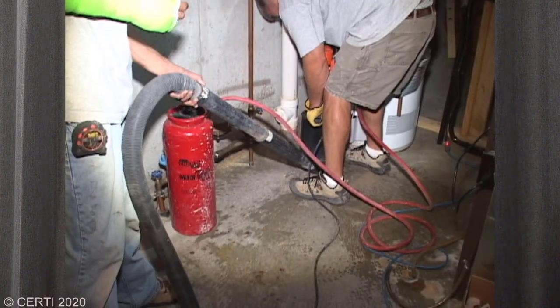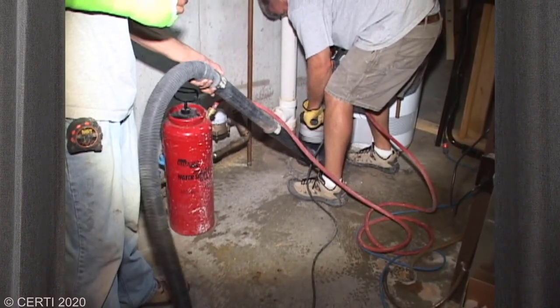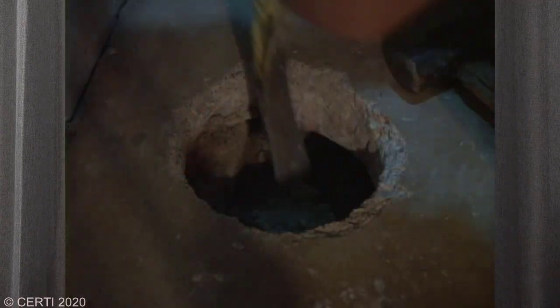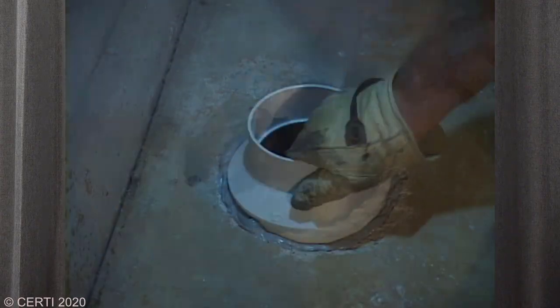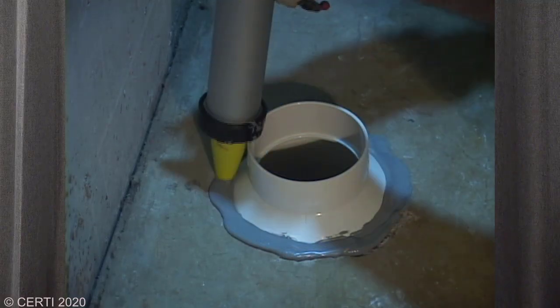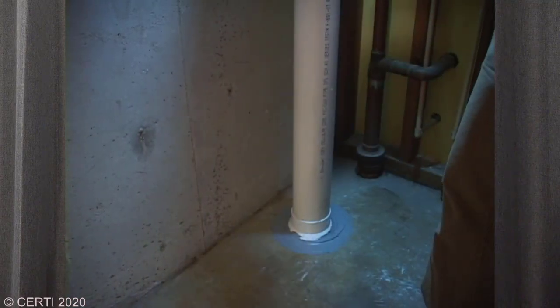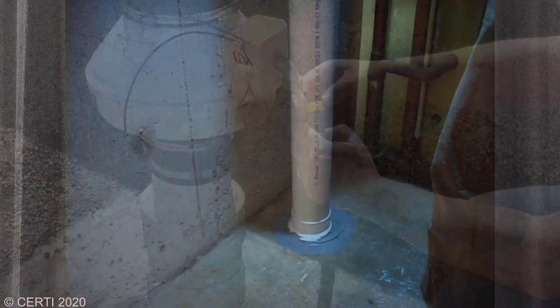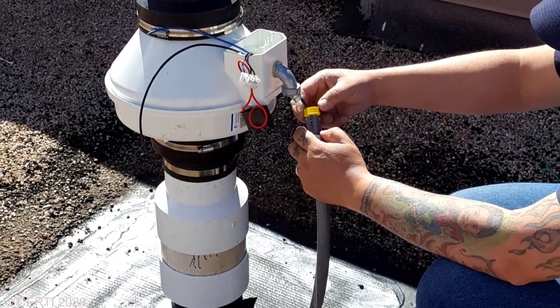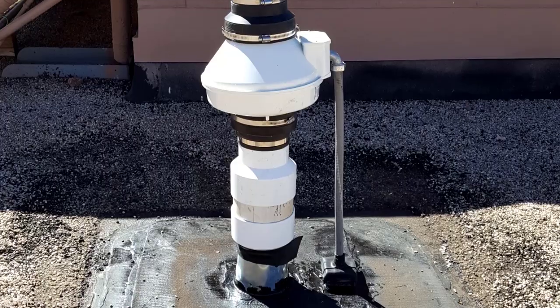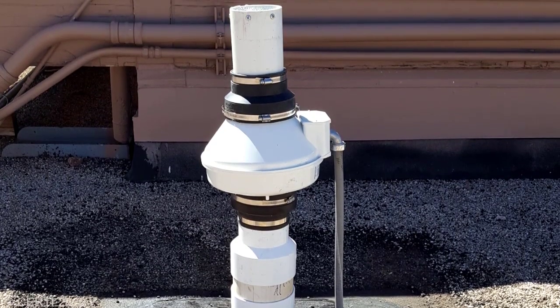For a slab foundation, a hole is cored through the slab at a strategic location. A couple buckets of dirt are hand excavated. A PVC pipe, typically 4 inches in diameter and not sheet metal, is connected to the hole and routed to a fan located outside the building envelope, with its exhaust point located above the roof and at least 10 feet from a building opening and 25 feet from a mechanical intake. After all, you wouldn't want to go to all that work and allow the exhausted radon to come back into the school.